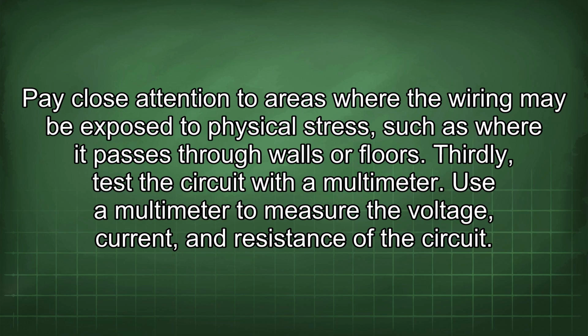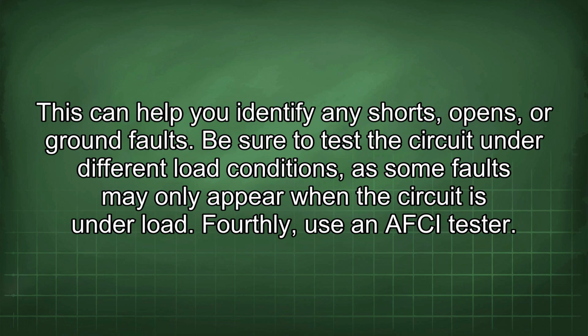Use a multimeter to measure the voltage, current, and resistance of the circuit. This can help you identify any shorts, opens, or ground faults. Be sure to test the circuit under different load conditions, as some faults may only appear when the circuit is under load. Fourthly, use an AFCI tester.